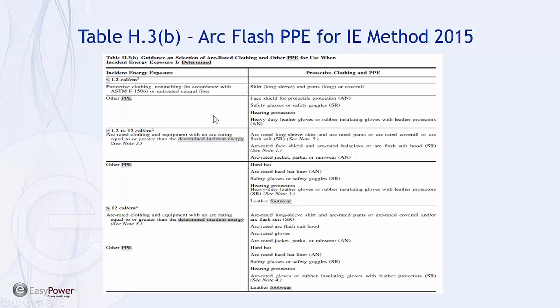Now, if you recall, this was Category 0 before, so at the end of the day, I'm going to argue it really hasn't gone anywhere. It has basically a different condition to getting there, and we're calling it something different. When we get to Category 1.2 to 12 calories, now we have a description of what the PPE needs to be. The big difference here, though, is we can actually suit up to the arc rating that we've calculated.